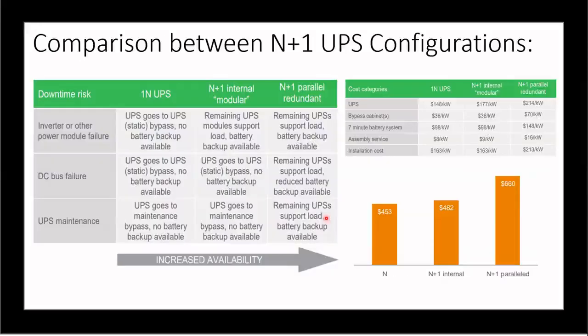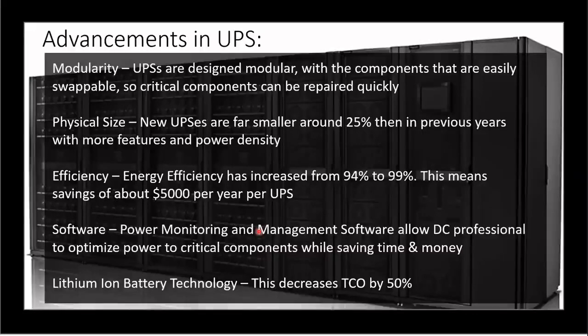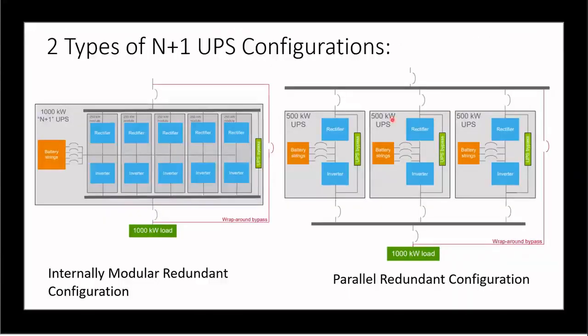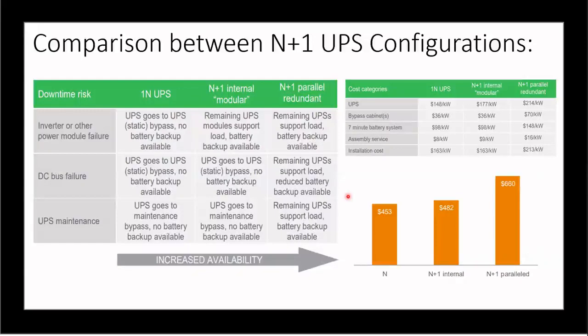And also the UPS maintenance. If we don't have redundancy, then we have to shut down the UPS completely. If the UPS is under maintenance, then no battery backup is available. But here there is battery backup available, right? Because here we will have the maintenance bypass that will pass the power and supply power to the load.